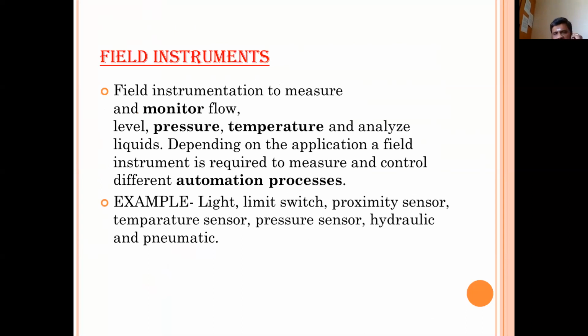Okay. So coming to the field instruments, what is meant by field instruments? If you see an industry, there will be a separate control room. The room is well equipped with AC and controllers, all the things, that is PLC and DCS, mostly the DCS. It will be part of the unit, so it will gather the information from the field. What is the field? Actually, field is nothing but the shop floor, where the manufacturing is happening, where the process is happening. That is the field.